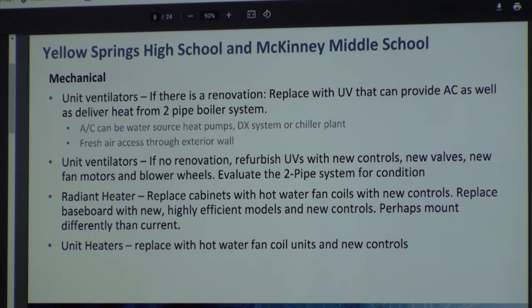My caveat on using the two-pipe system for heating and cooling is the condition of the pipes. They're old. We can take a coupon out of a few sections and take them to a lab, they can test them and come back and say it's fine. Most of the time we get good results, even on old copper. Is it copper or steel? I think it's all steel.